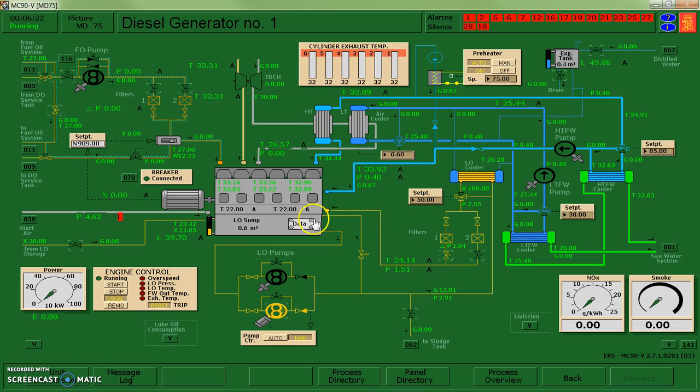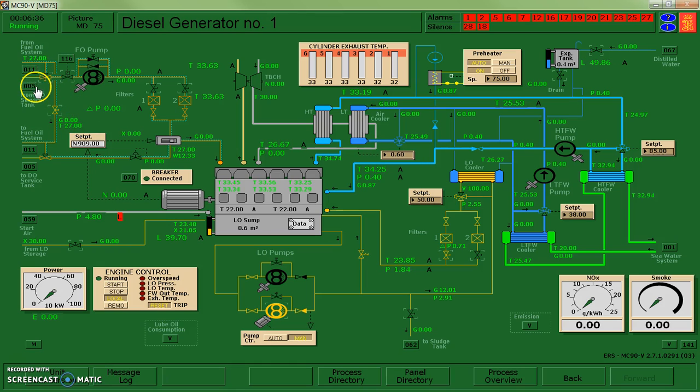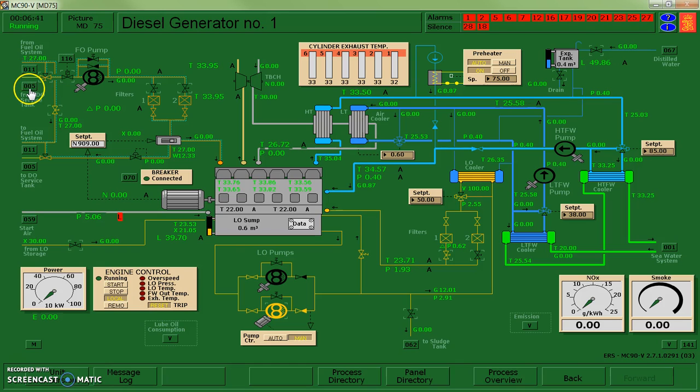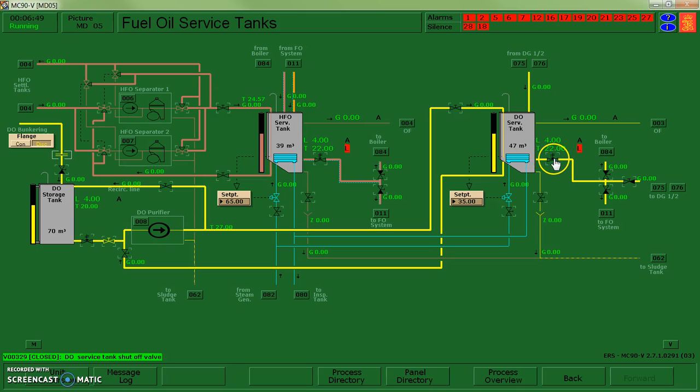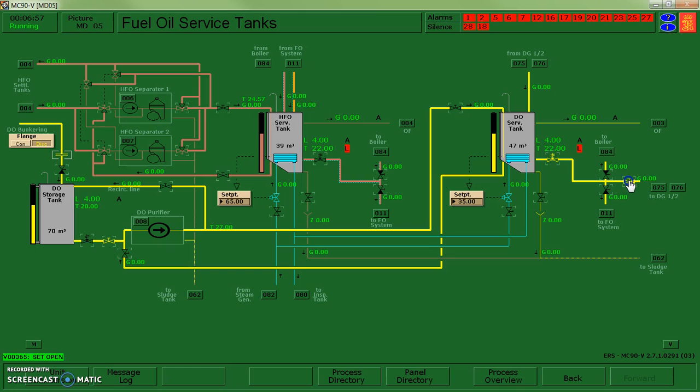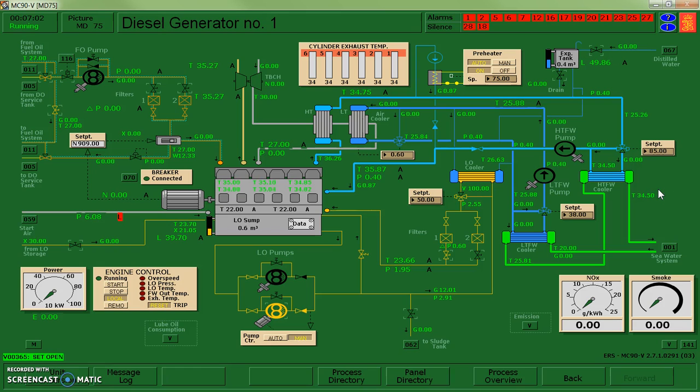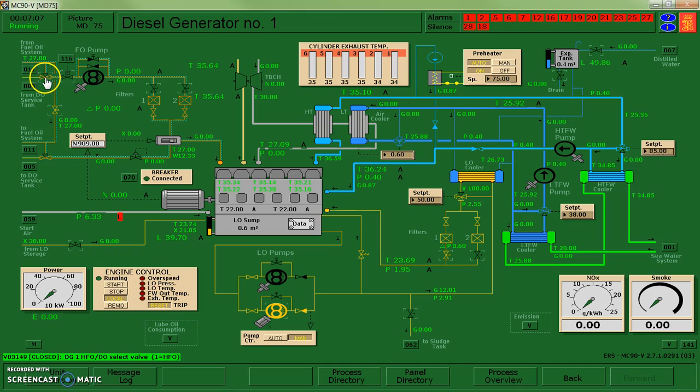Next let's look at the fuel system. So fuel, I've got two places that fuel can come from, 5 and 11. I'm going to come from 5 at this point. So let's go over there. What we see is we have our diesel oil service tank. A couple of valves to get there. So I have this emergency shutoff valve, quick acting valve to open, and then another valve to get to my DG1. That brings me to this point.